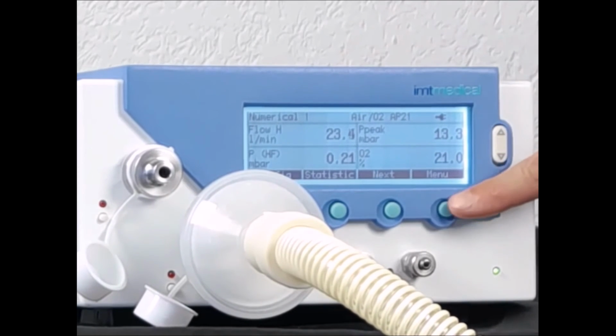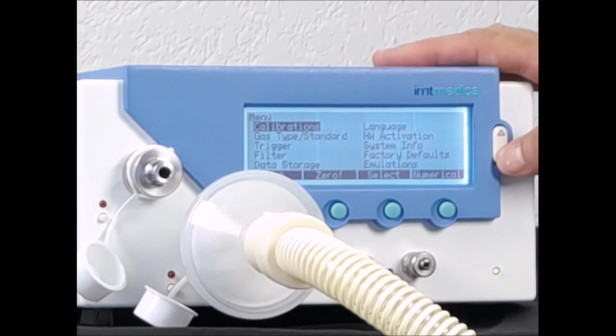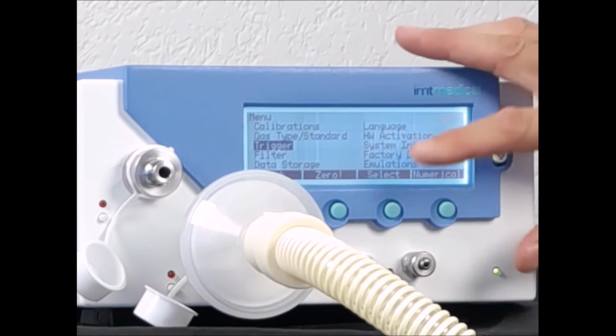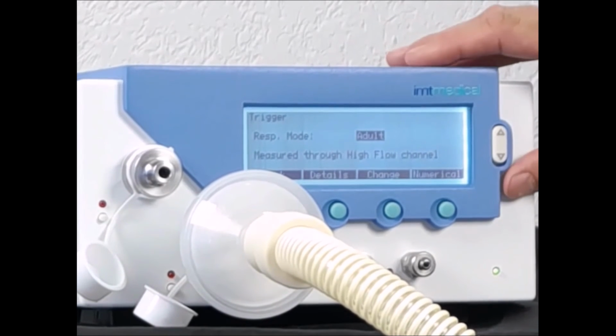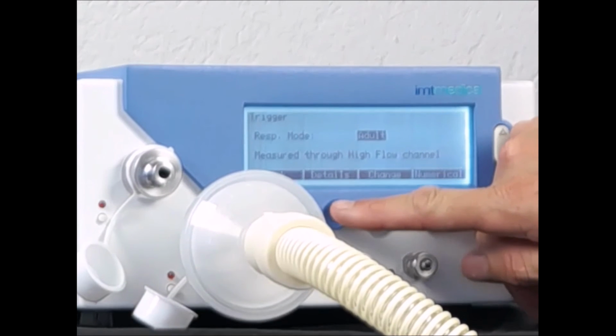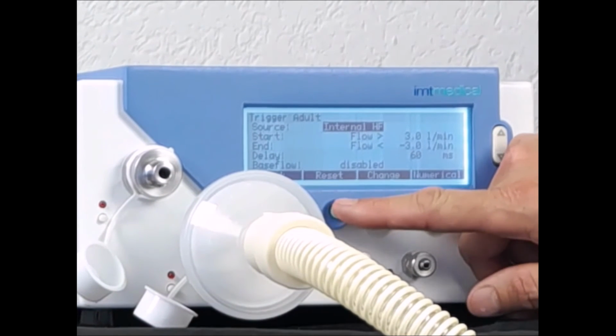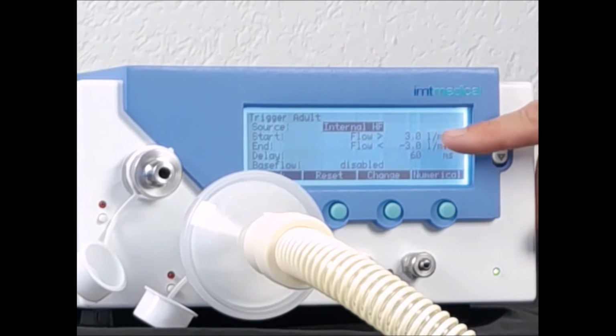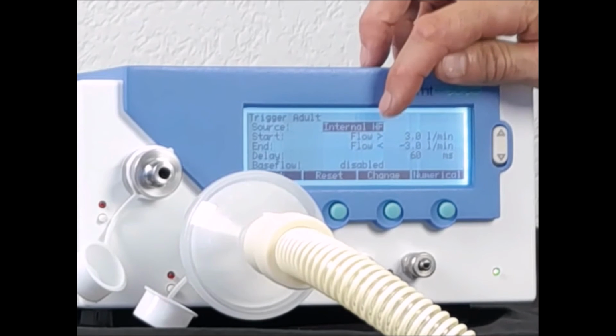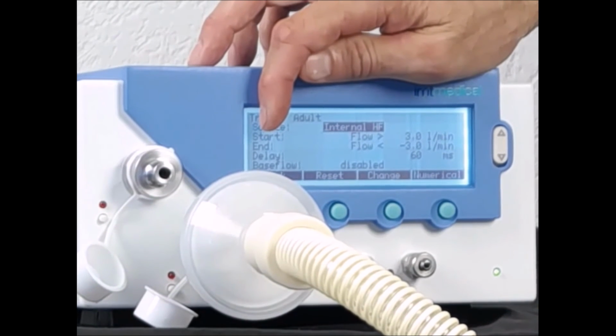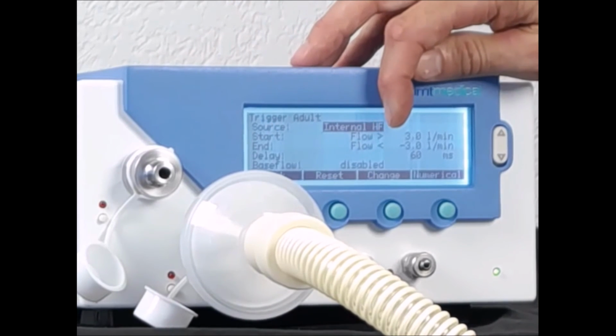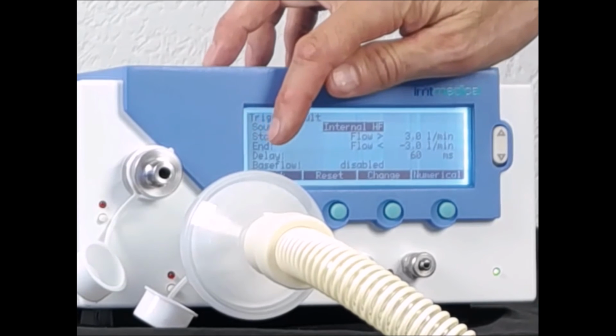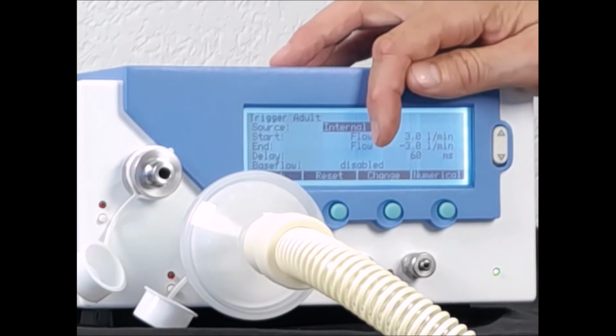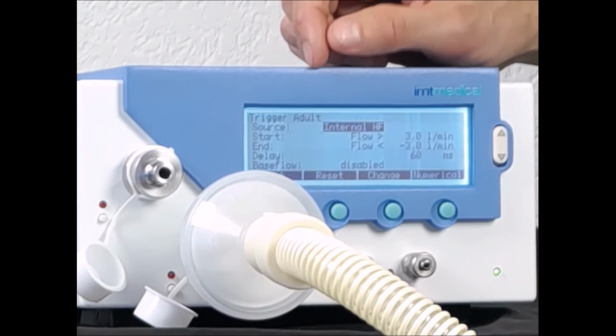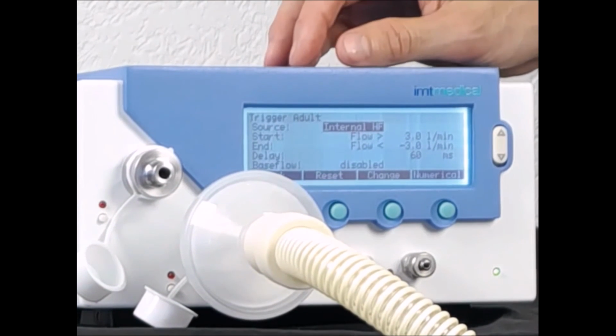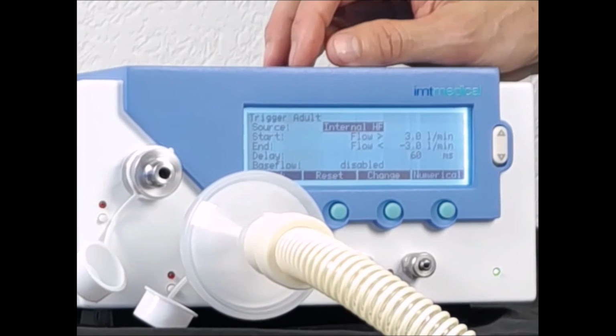Next, I want to see the trigger settings because I want to check adult ventilation. I check the trigger, I select it. It is now set to adult. I can quickly check on the details if nobody has changed anything. I have a start trigger, flow plus 3 liters per minute, rising edge, and I have an end trigger, which is the trigger at the start of expiration, of flow falling edge minus 3 liters per minute. Delay is 60 milliseconds, and base flow is disabled. To get more details on these settings, please check our other video, which deals with ventilation parameters and trigger settings.